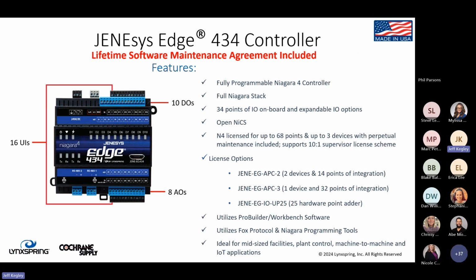The 434 is the first product in the lineup. Physically, it's the same as the 534, just with different licensing as described—lifetime SMA included. Because it's not an integration platform, there won't be a wide variety of number of devices and points. You'll see on the screen the license options: APC2 with 2 devices and 14 points of integration, APC3 with 1 device and 32 points of integration, plus 34 points of onboard I/O. When you need to expand that I/O, there's an adder for additional hardware points when you buy the adder modules. That's the 434.